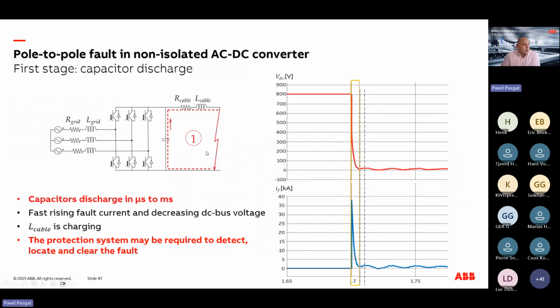stage, after a short circuit occurs, the capacitor will react the fastest. And what is going to happen is we are going to have a capacitive discharge, which is this first part. And you can see the peak is very high. In this case, it's almost 40 kiloamperes, but in large DC systems, 500 kiloamperes is not unheard of as a prospective short circuit current. But then it drops off very quickly.